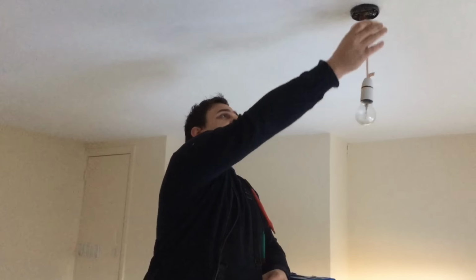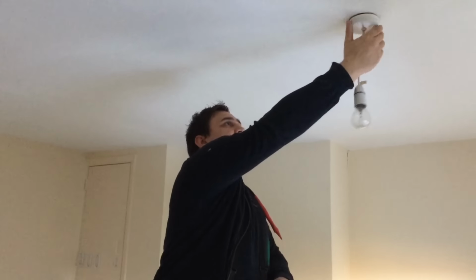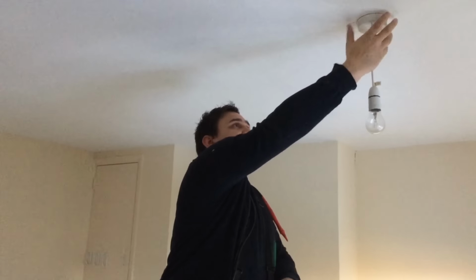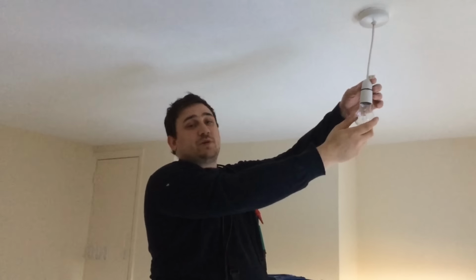Now we're going to return all the covers back to where they were to do the insulation resistance test. We're also going to leave all the switches in the on position and remove the loads because we don't want them to affect our insulation resistance reading.